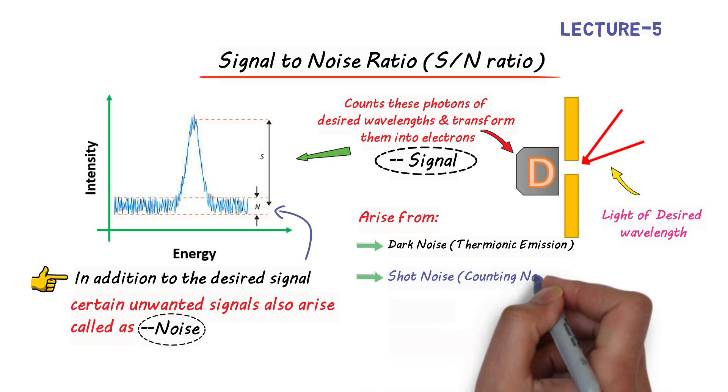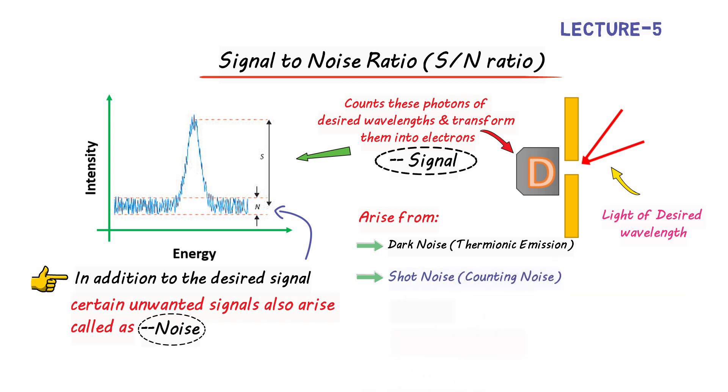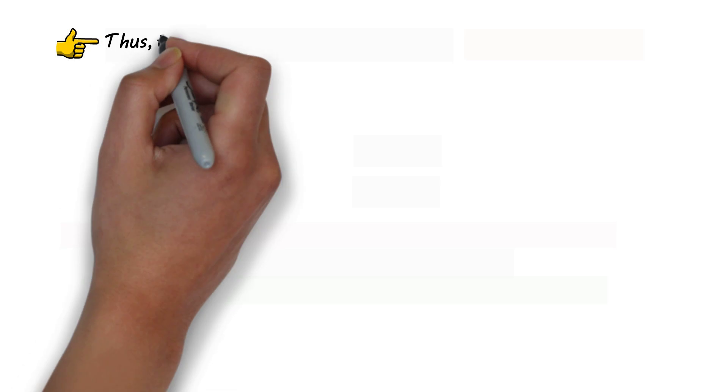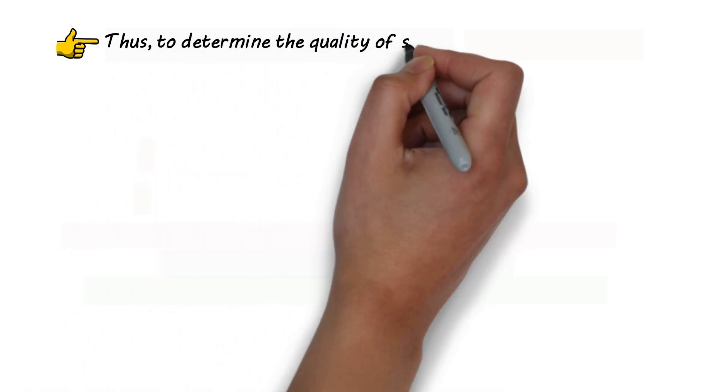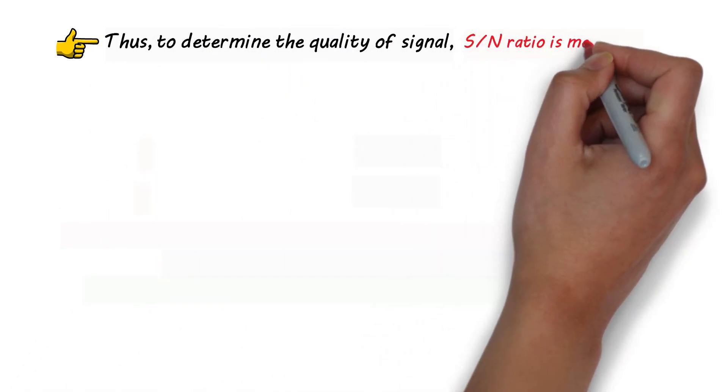Third, noise can also arise from stray light passing onto the detector. And finally, we can have instrumental errors that result in noise formation. Thus, to determine a good quality signal, signal to noise ratio is measured.